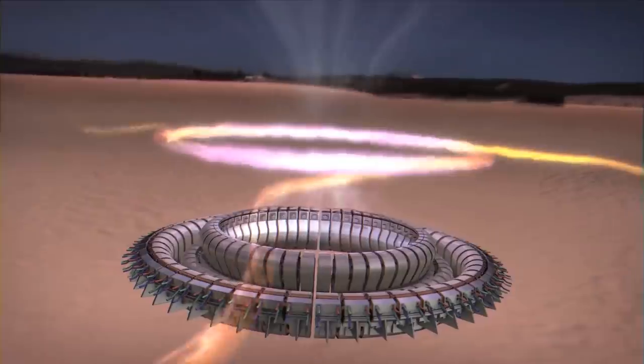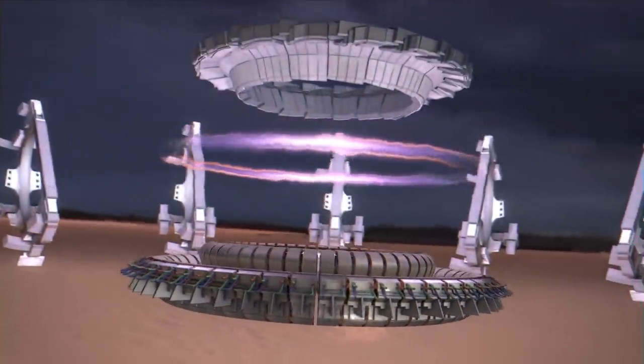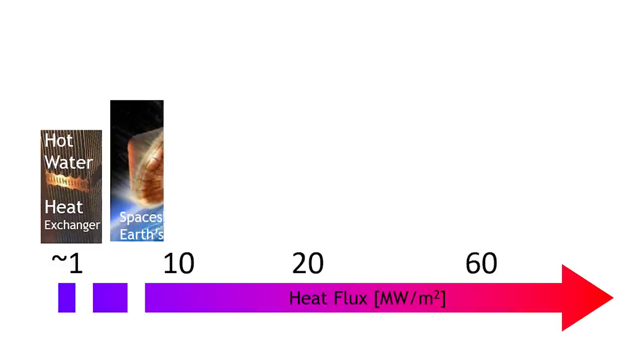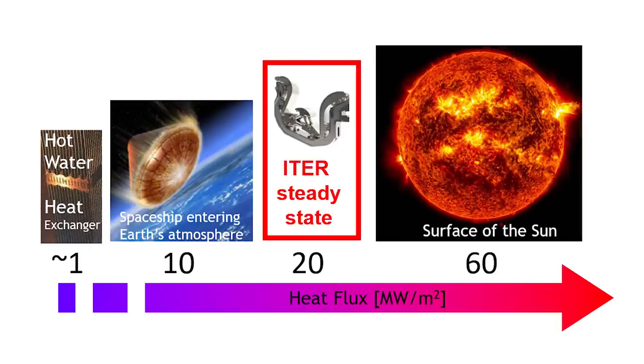The divertor is like a heat exchanger, because this is the place in the tokamak where the particles finally touch the wall and generate fantastic heat — up to 20 megawatts per square meter in our load specification. That is incredibly high. So you need technology able to extract this power, which is on one hand very robust and on the other hand quite innovative.